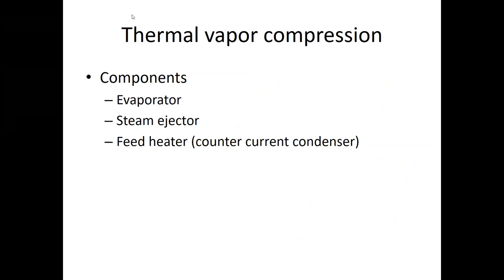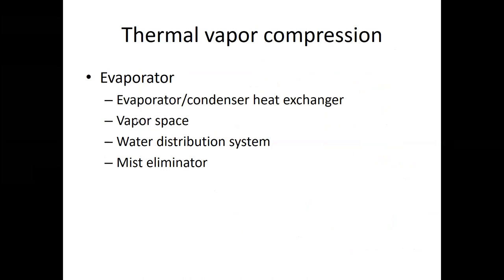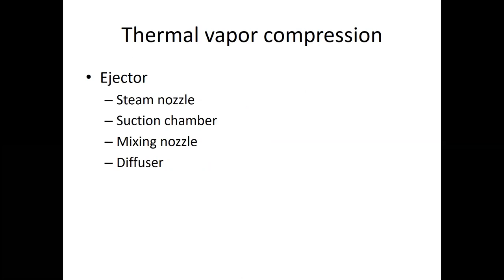The system components are: evaporator — with a heat exchanger tube bundle, space for vapor formation, spraying nozzles for seawater, and a mist eliminator to prevent seawater droplets from being carried out by the vapor; and the ejector — with a steam nozzle, a suction chamber for entraining vapor, a mixing zone where motive steam mixes with entrained vapor, and a diffuser where velocity decreases and pressure increases. That's why it's called the thermal vapor compressor: we compress the vapor without any moving part using just the diffuser.